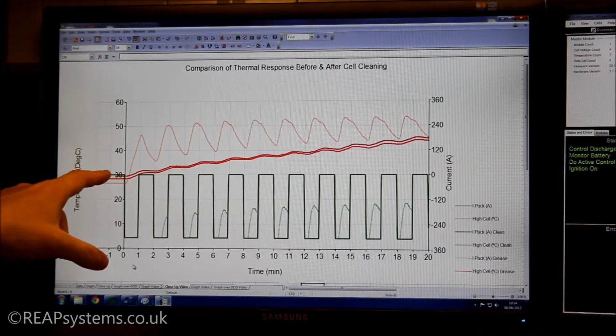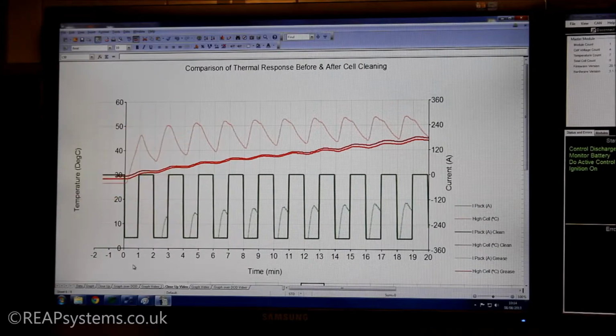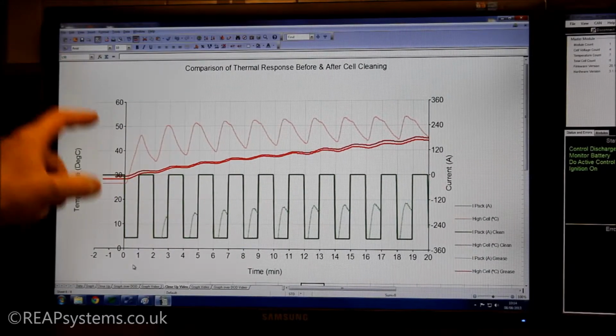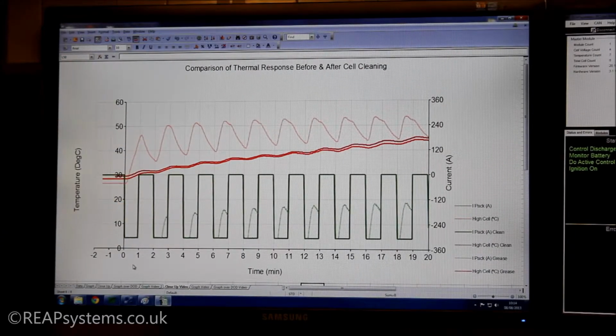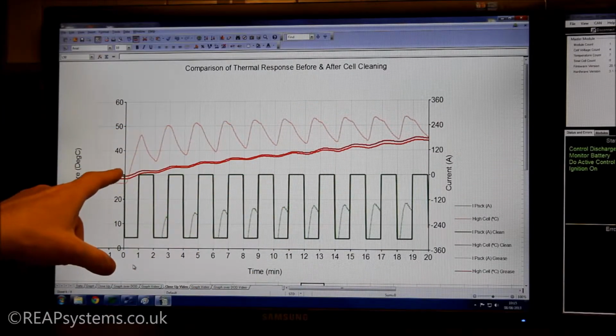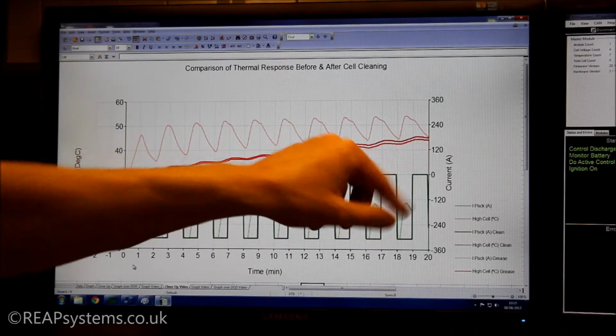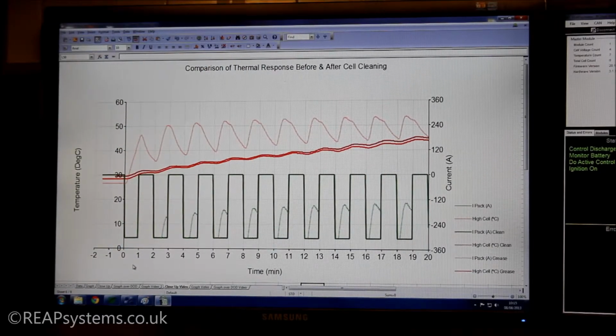Okay, so what's happening to the temperatures then? Well, the dotted line there, which is really jumping up very quickly, shows us the highest temperature on the uncleaned pack. So very quickly, the BMS has to respond to high temperature, and it reduces the allowable discharge current. And this goes up to 55 here on the first 10 cycles, whereas on the cleaned contacts it's going up to only 45. So this means no limitation for the cleaned modules.